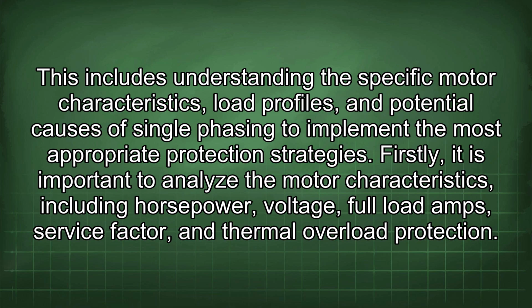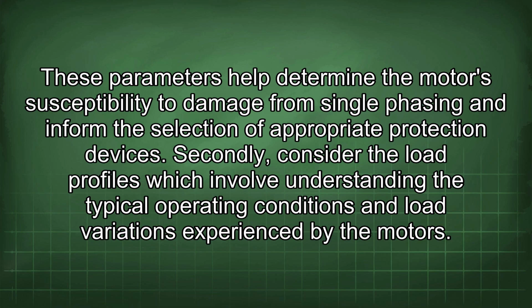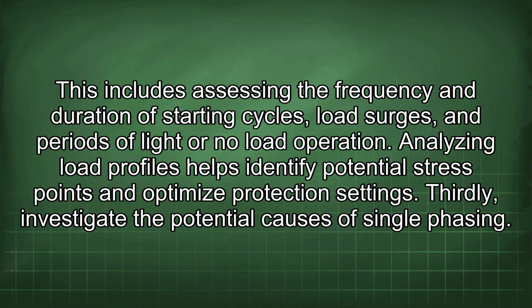protection strategies. Firstly, it is important to analyze the motor characteristics, including horsepower, voltage, full load amps, service factor, and thermal overload protection. These parameters help determine the motor's susceptibility to damage from single phasing and inform the selection of appropriate protection devices. Secondly, consider the load profiles, which involve understanding the typical operating conditions and load variations experienced by the motors. This includes assessing the frequency and duration of starting cycles, load surges, and periods of light or no load operation. Analyzing load profiles helps identify potential stress points and optimize protection settings.